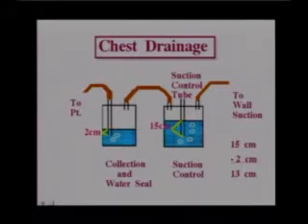And we need to look at the bubbles again. In the suction control, there are bubbles. And these bubbles come from air being pulled in here to equalize those pressures. So these bubbles come from air being pulled in. These are continuous bubbles because this is continuous suction.